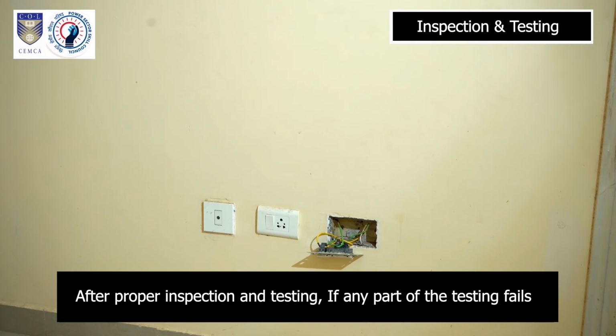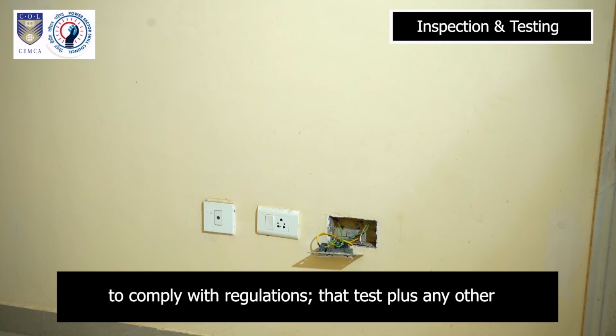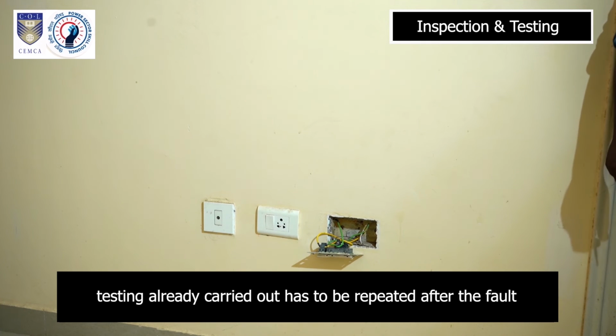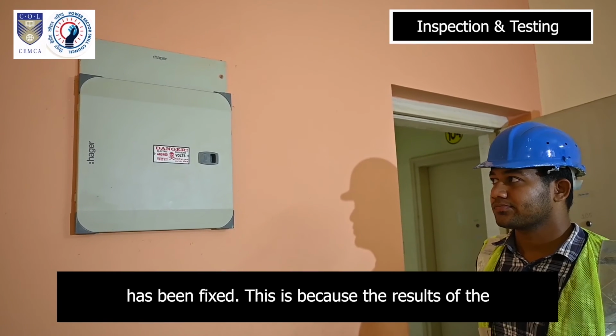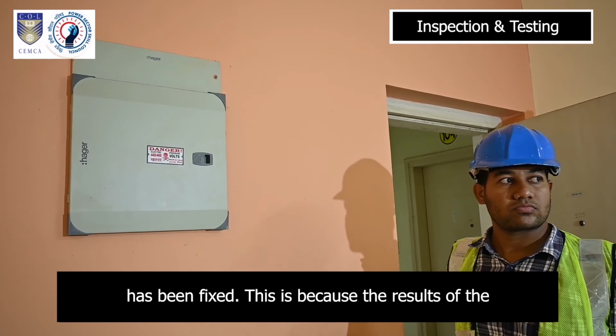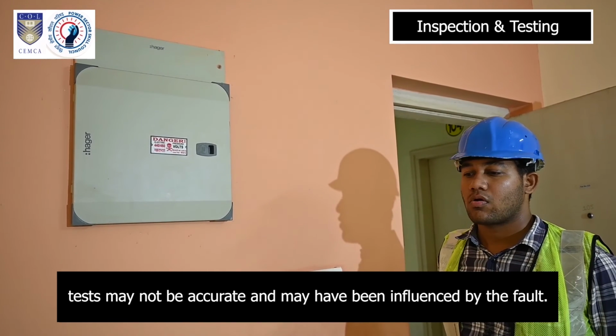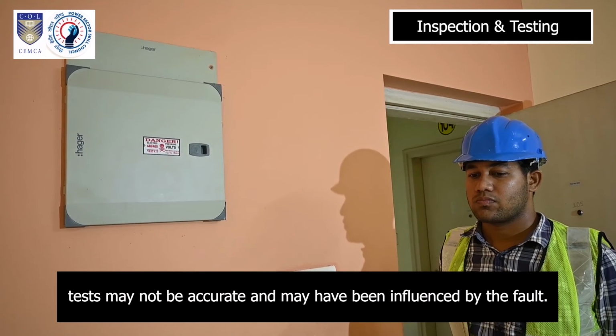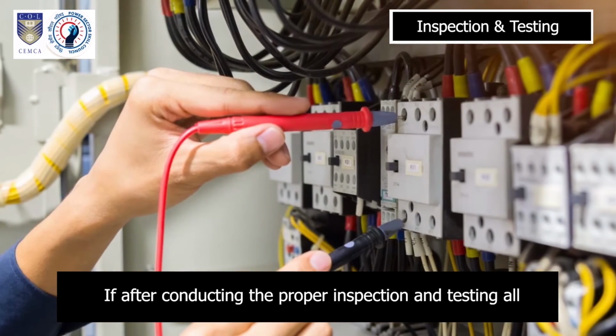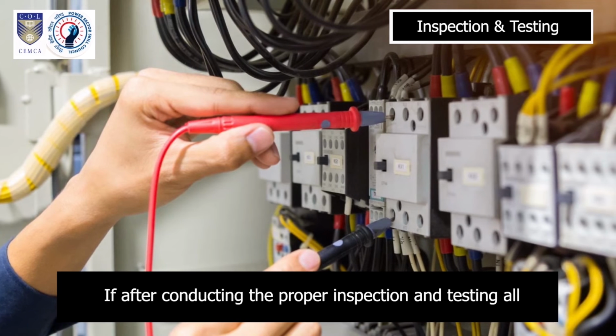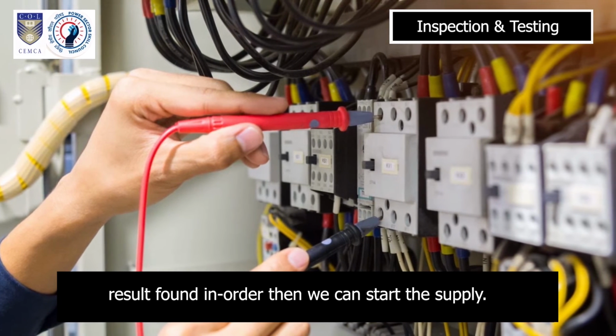What do we do after inspection and testing? After proper inspection and testing, if any part of the testing fails to comply with regulations, that test plus any other testing already carried out has to be repeated after the fault has been fixed. This is because the results of the tests may not be accurate and may have been influenced by the fault. If after conducting the proper inspection and testing all results are found in order, then we can start supply.